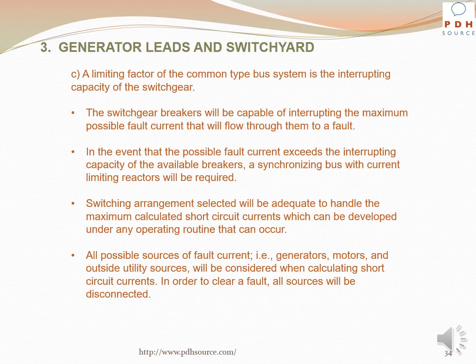A limiting factor of the common type bus system is the interrupting capacity of the switchgear. The switchgear breakers will be capable of interrupting the maximum possible fault current that will flow through them to a fault. In the event that the possible fault current exceeds the interrupting capacity of the available breakers, a synchronizing bus with current limiting reactors will be required.